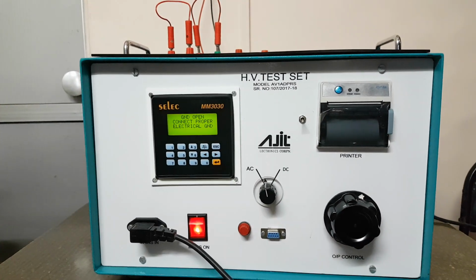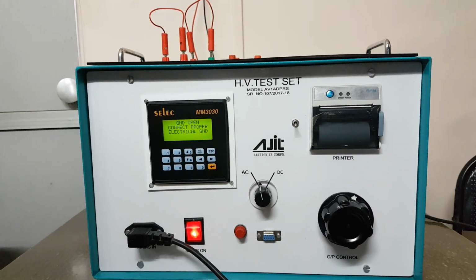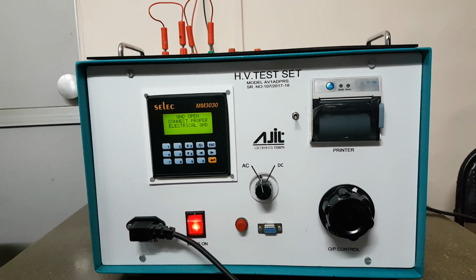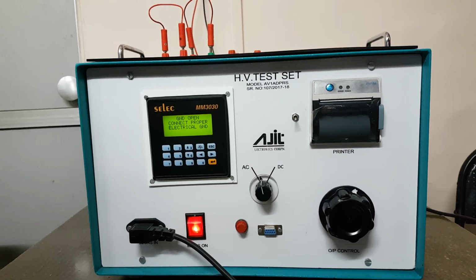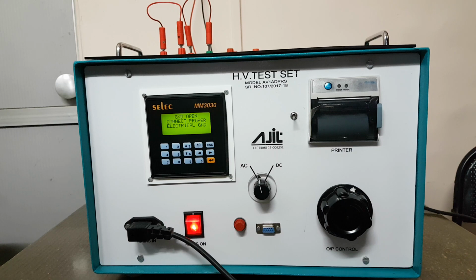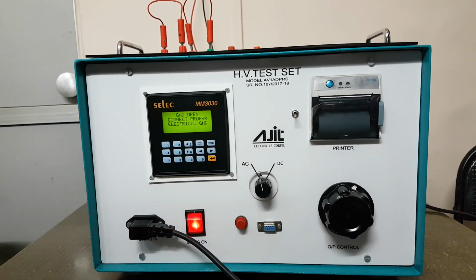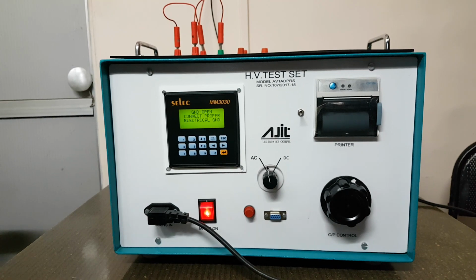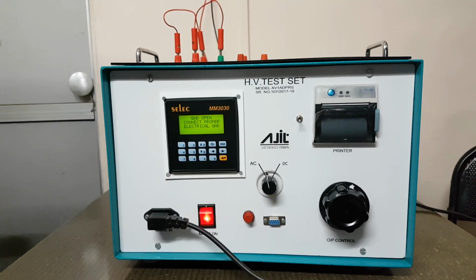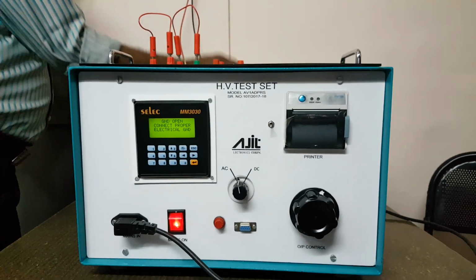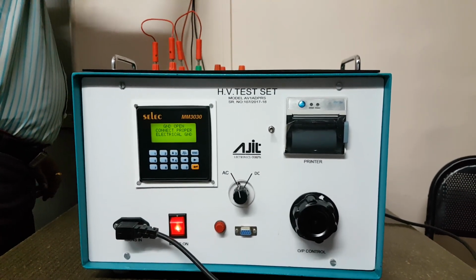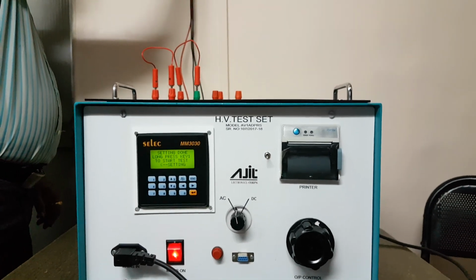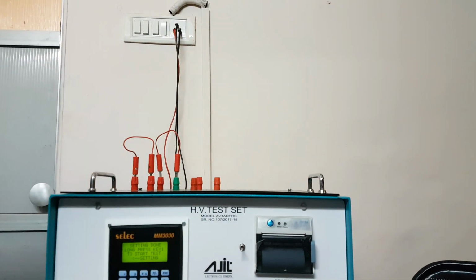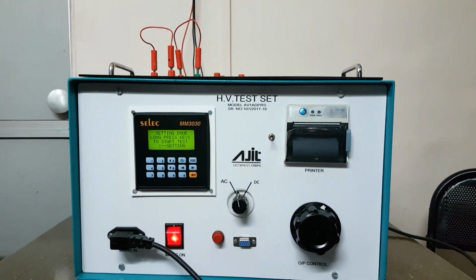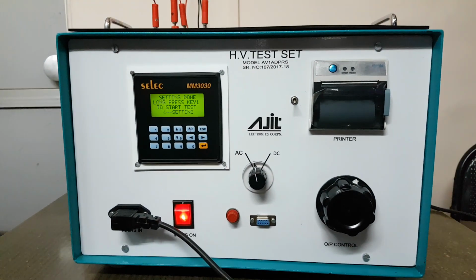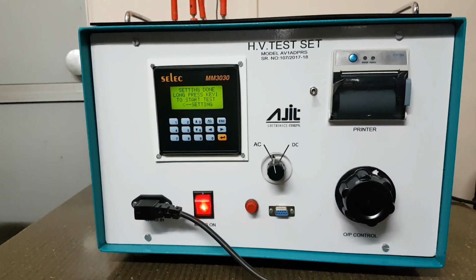This means we have not connected ground to the instrument, and the instrument has an interlock that unless we connect the electrical ground properly, the instrument will not move ahead and it will display this message. Now let us connect the ground and see what happens. Now this interlock has worked, and once the ground is provided, the instrument has moved ahead.